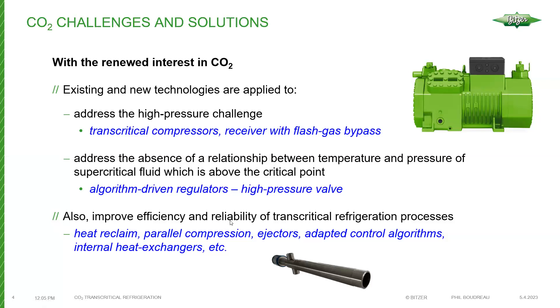In areas where you're running subcritical most of the time, it's just a matter of running in transcritical mode for several hours during the year — a very small percentage of total annual hours. Technologies to reduce energy input include heat reclaim, parallel compression, ejectors, adapted control algorithms — which are constantly being improved — and internal heat exchangers.